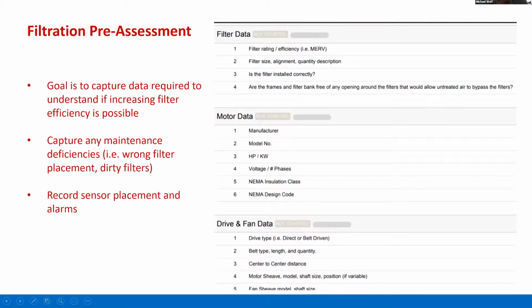And then finally, I just want to highlight making sure this all ties back to that OPR CFR conversation. So after you implement that commissioning approach, whether it's a new building or existing building, make sure to revisit that OPR CFR document. With this campus example, we ended up finding that they wanted to pursue MERV 13 filtration, but MERV 13 filters, as many of you know, are 8, 9, 10 months out in terms of lead time. So that just isn't feasible for them to get the quantity they need. So looking at other solutions, and redocumenting those expectations in that OPR, that can be a tool that communicates upwards to those executive level, maybe more of a non-technical audience.